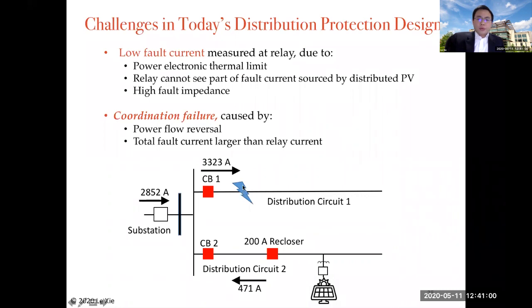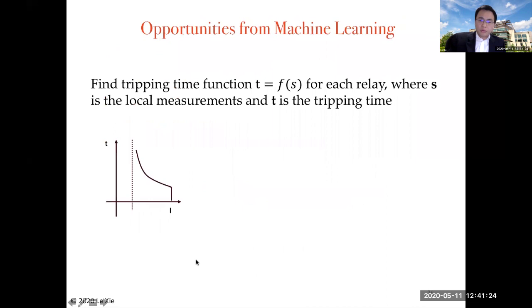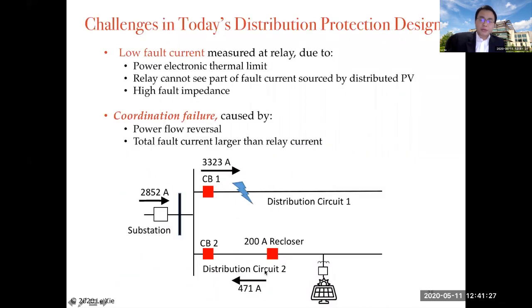Here's another example. If you have distribution circuits in parallel, circuit 1 and circuit 2, and a fault happens in the circuit breaker 1 area, the voltage at circuit breaker 2 is still fairly large because there's a solar panel at the end of the feeder line. That's going to inject a major current back to circuit breaker 2, and that current might be substantially higher than the threshold of the recloser on circuit breaker 2. In other words, a faulty situation in another location may cause the recloser on circuit breaker 2 to malfunction — which should not have happened.